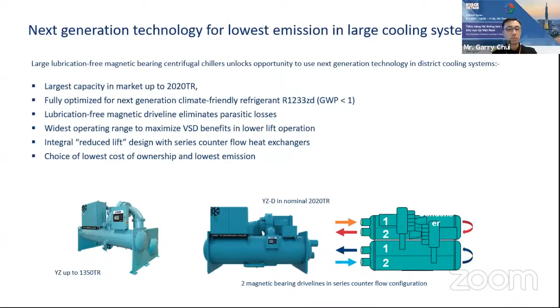Because of the Kigali agreement and the upcoming HFC phase-down, this new generation of centrifugal chillers is designed with low-GWP, climate-friendly refrigerants. Magnetic bearing technology has been available for smaller sizes in the past few years, and now we've expanded the range so this future technology is also available for district cooling systems.